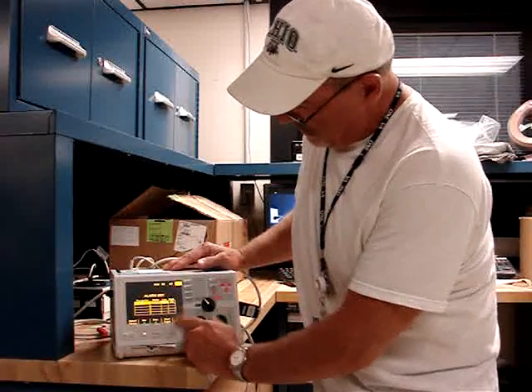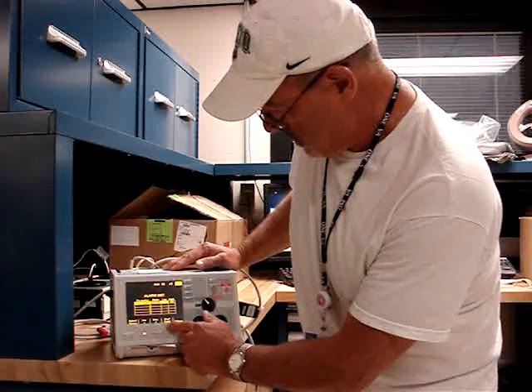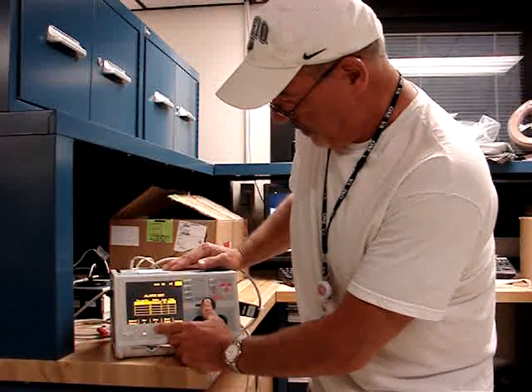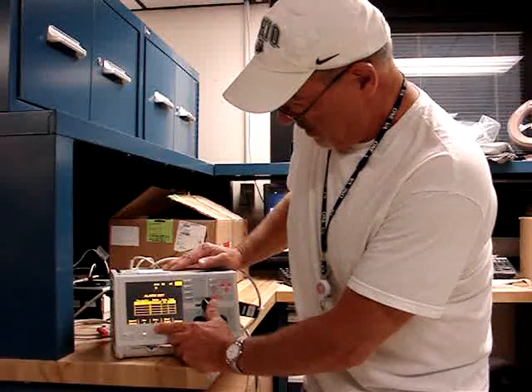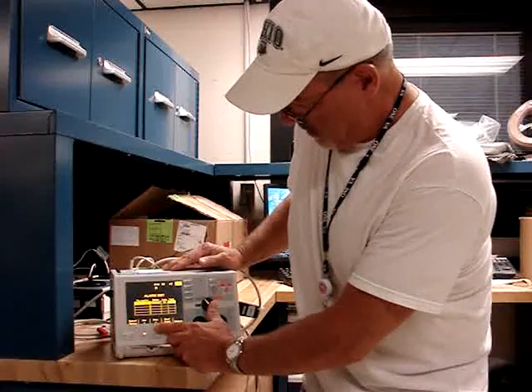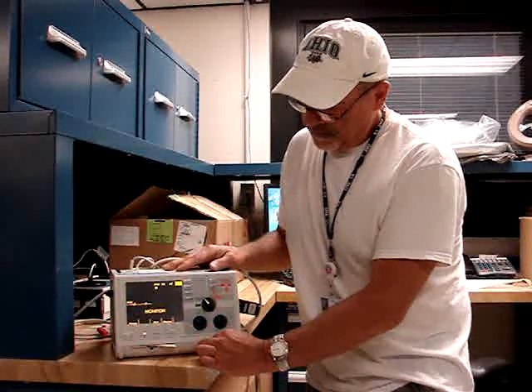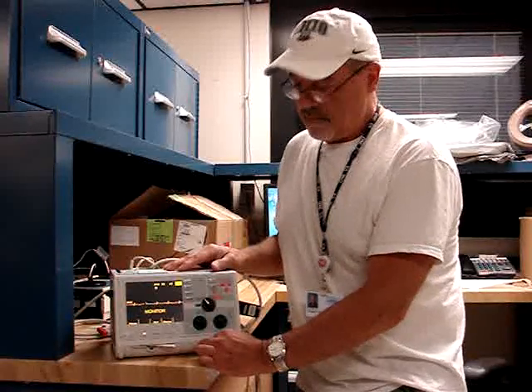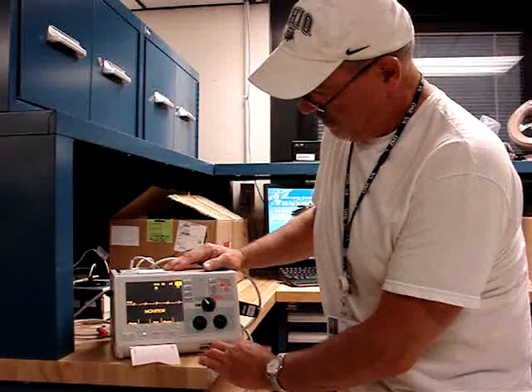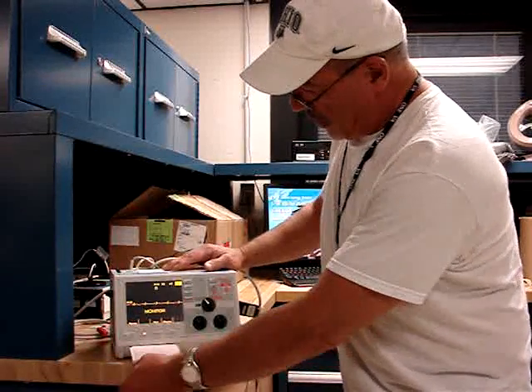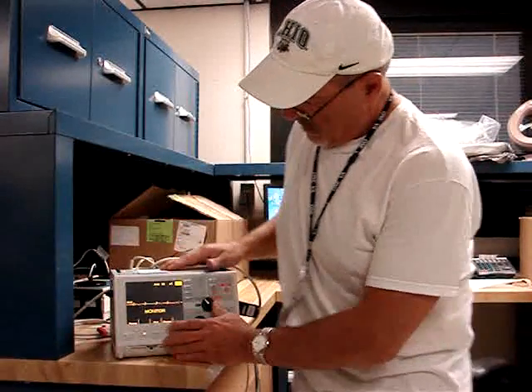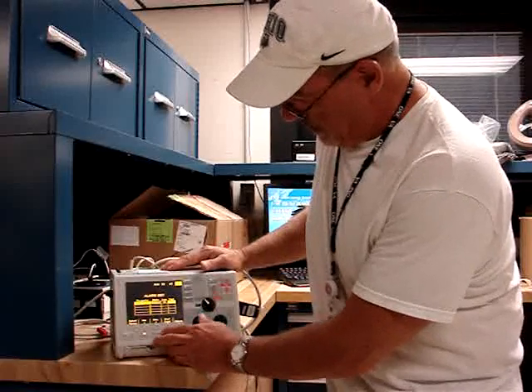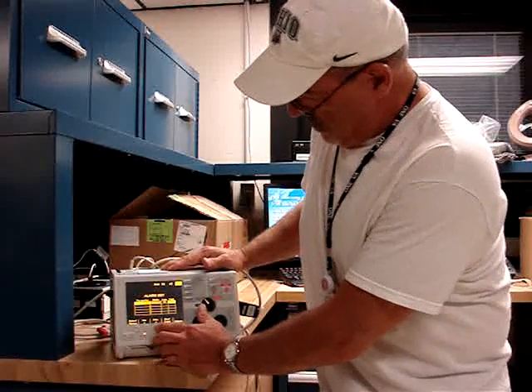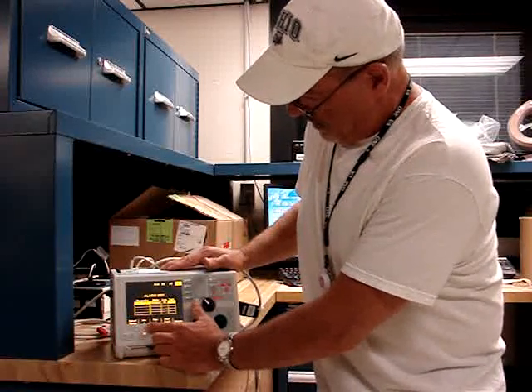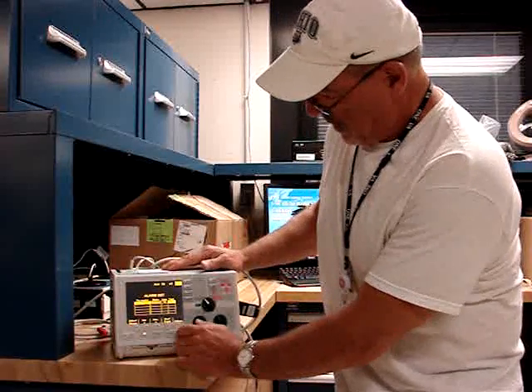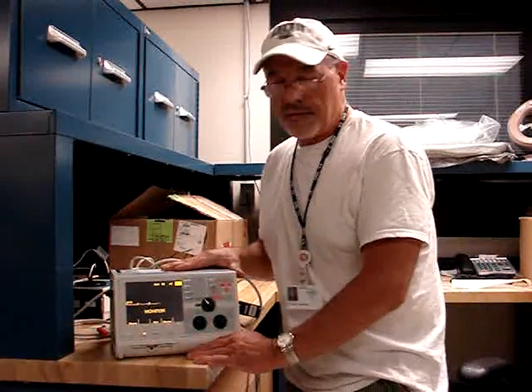Okay, now we're going to take the high side down over to 70. Return. There we go. Okay, we got a recording. Suspend the alarm. And we'll go back and reset it. Take it back up to 150, and then return, and that takes care of the alarms.